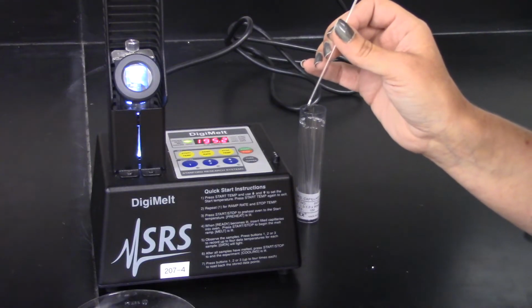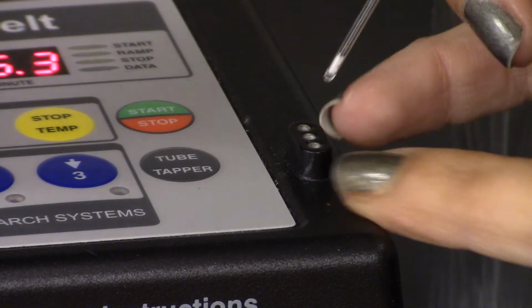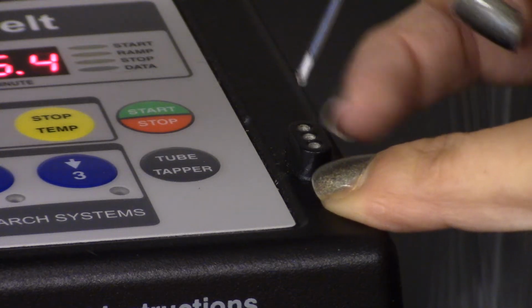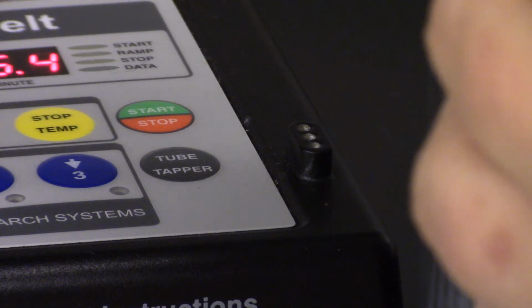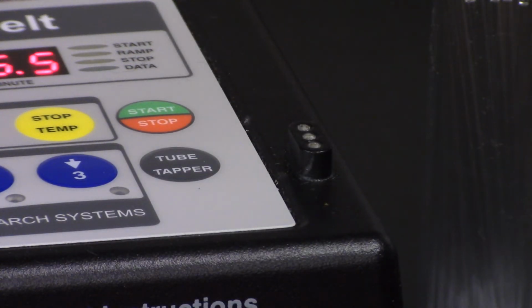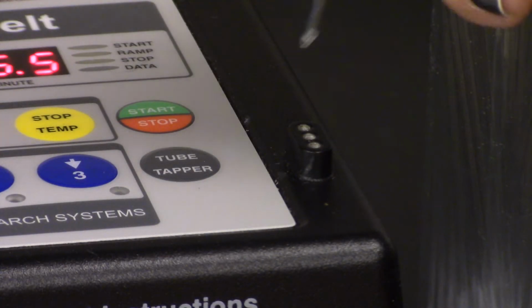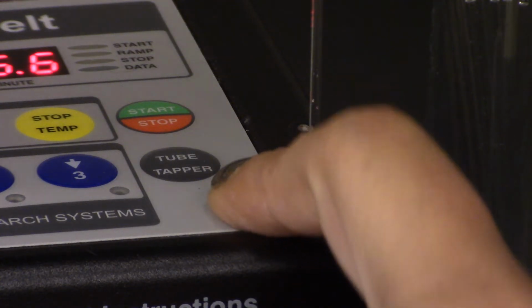And so I'm going to zoom in for a second here on the DigiMelt. There are 3 little holes here that will each accept a melting point tube. You just put it in with the bottom end, and I'm actually going to put a little bit more in here because it actually fell out. That actually fell all the way in.